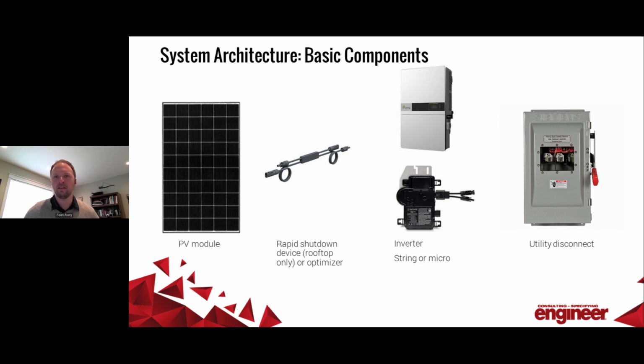To the right of that, we have some examples of some solar inverters. These are converting the DC electricity to AC electricity that's needed for the building to use. Most predominantly, I see string inverters, which is the example on the top, and I'll show you a wiring diagram of this in a minute. But they're generally in the scale of 25 to 100 kilowatts in size. And then below that is a micro inverter example, which would be used for, again, every 1 to 2 modules would have its own little inverter there. And there's pros and cons to each one.